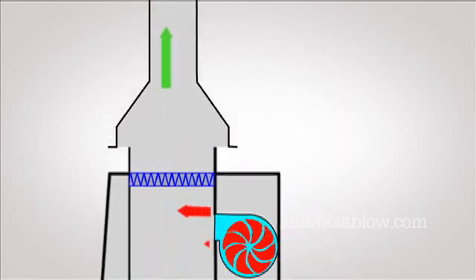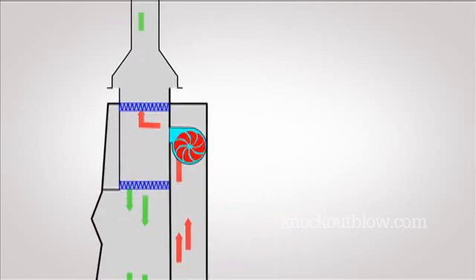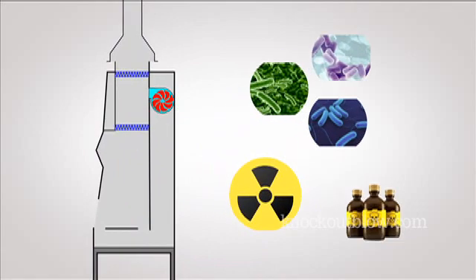The recirculated and downflow air is vented outside through a canopy unit. Therefore, the cabinet can be used with biological agents containing minute quantities of toxic chemicals and trace quantities of radionucleotides without interfering with work.